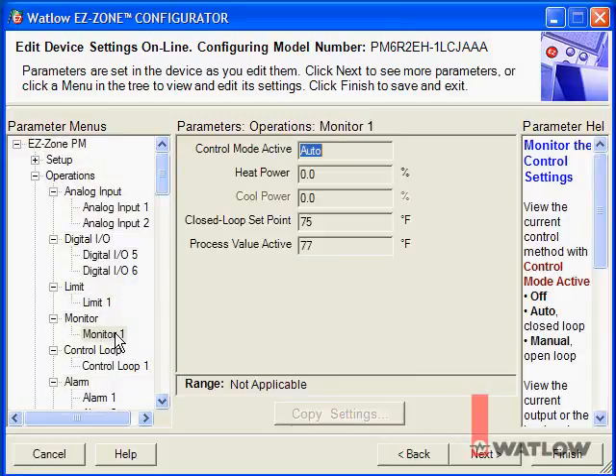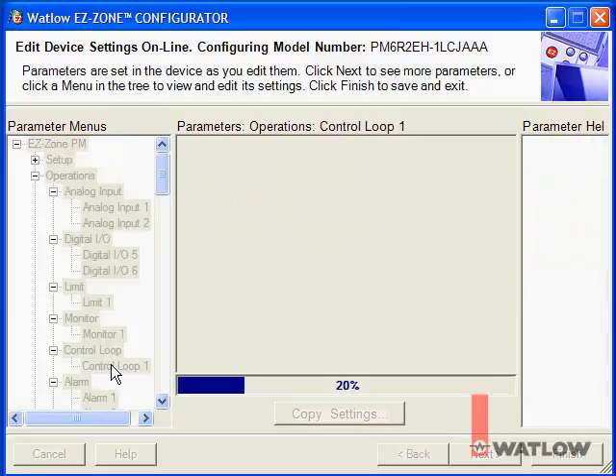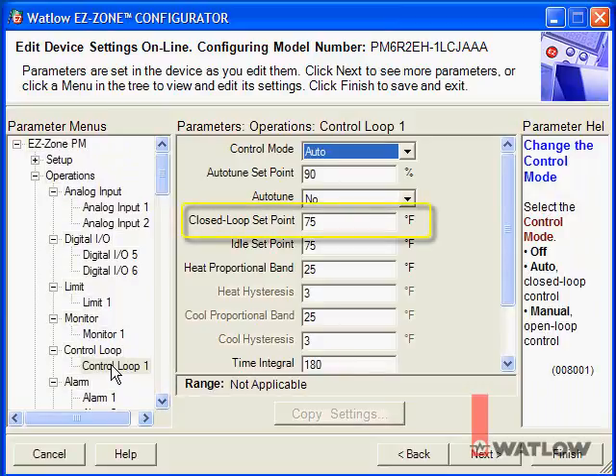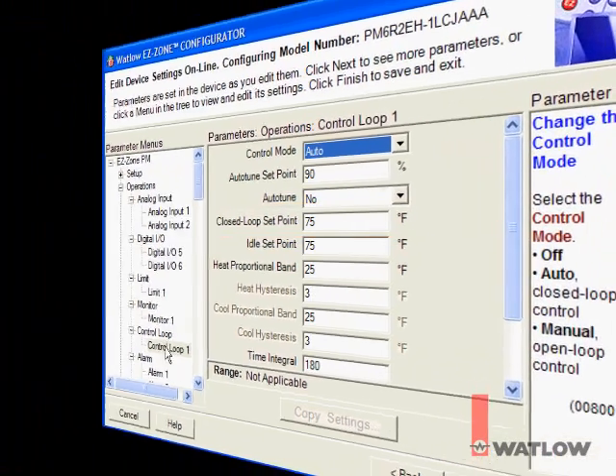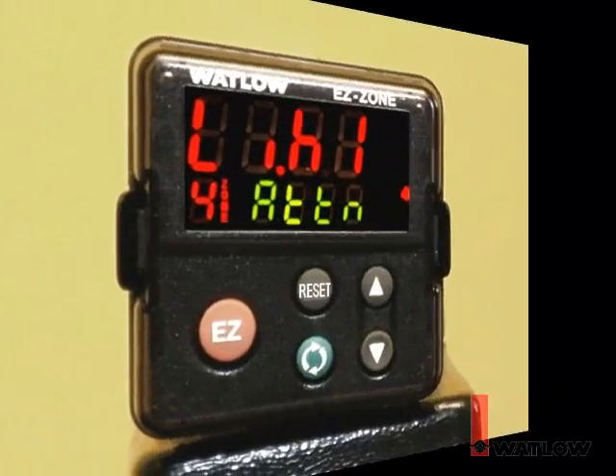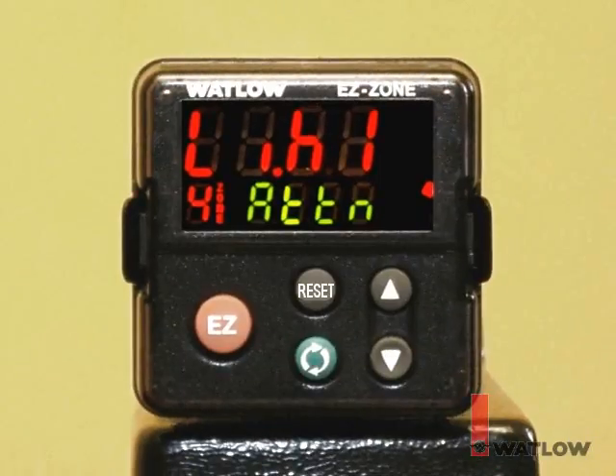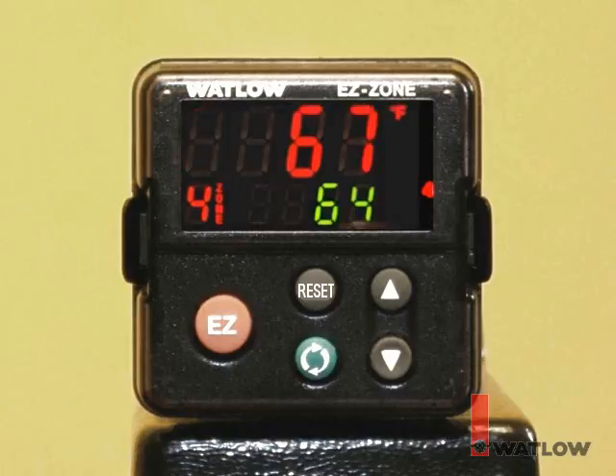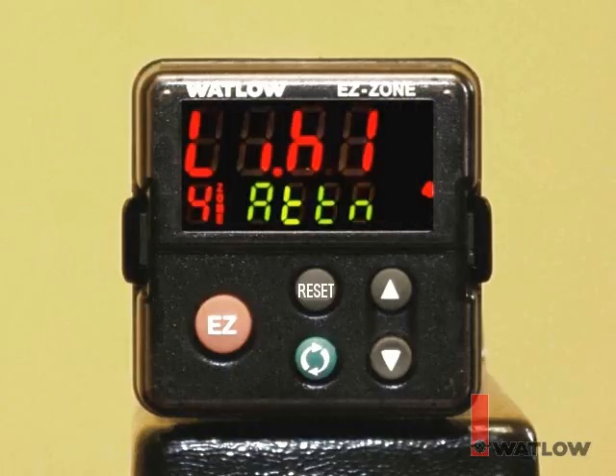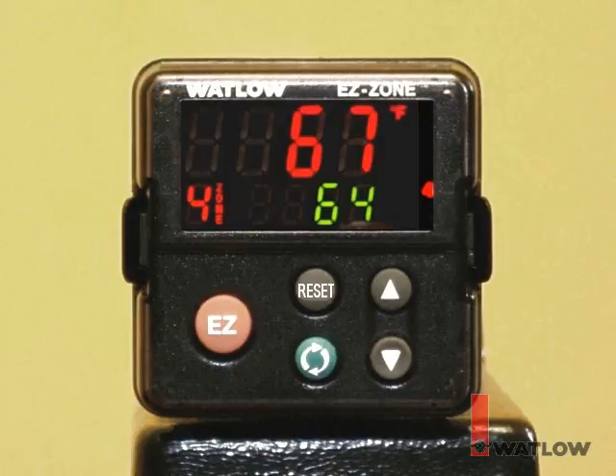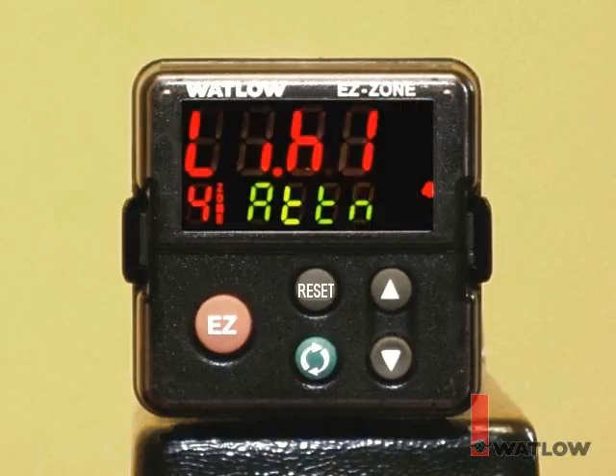On the Monitor 1 menu, you can see what the control loop is doing, which isn't much since we haven't set the setpoint yet. On the Control Loop 1 menu, you can set the setpoint. Before changing it, consider if it's safe to increase the temperature. At this point we can't, because the controller is indicating a high limit alarm — that's been there all along because the default setting for the high limit is zero. Even though we've set the high limit to 275, the limit latches and does not reset by itself.